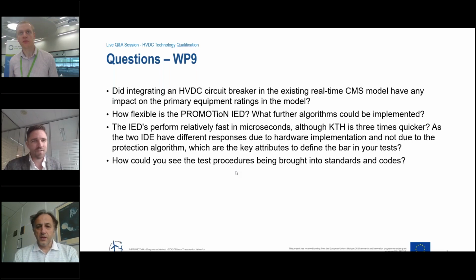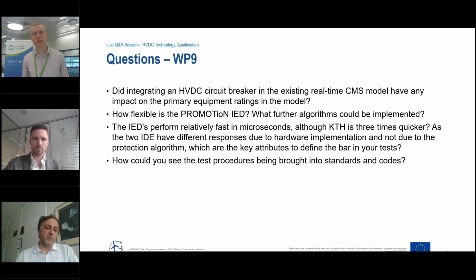Mario? Thank you, Cornelis. I think this will be a very challenging question for the future, especially because power system protection in HVDC is not only about protection operation of the relay, but also a combination of the protection and the circuit breaker operation. Whilst for AC breakers, a delay of several milliseconds in breaker operation will not be a problem, a delay of several milliseconds when the protection operates and the breaker acts could be a big problem.